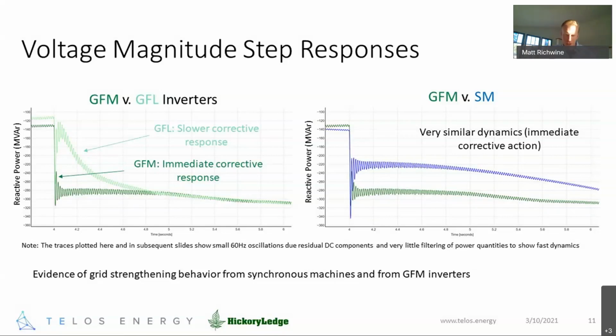One other quick comment, just so that it's not a distraction. For folks that maybe are not used to looking at plots like this in these time frames, you'll see a lot of wiggles going on at the fundamental power frequency, 60 hertz. They're small. These are generally expected due to slight offsets of DC or slight asymmetries. That is an aspect that shows up in EMT modeling, where you're looking at these things in very fine detail. A lot of folks may say, well, gee, I've run PSCAD simulations and maybe have not seen this. There's some filtering applied to some of these that we addressed explicitly, where we wanted to make sure that we were not filtering out too much and obscuring some of the fast dynamics. So that's a quick reason why some of those wiggles are showing up here.